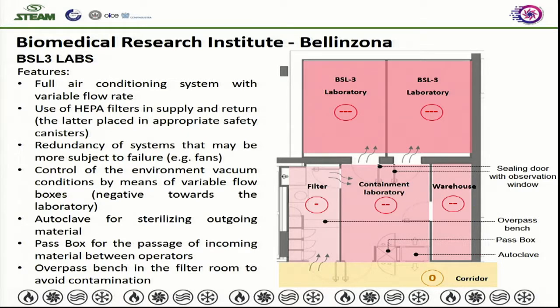The systems that can be subject to failure must be redundant, like fans, for example, and the control of the environment vacuum must be very, very accurate. You have always negative pressure, obviously, inside the BSL-3 laboratory. Like you see here, there is a pass box. All the materials that must be sent from outdoors to inside the laboratory must pass in this pass box to avoid contamination. All the materials that go out from the laboratory must be sterilized in an autoclave, and this is compulsory too.